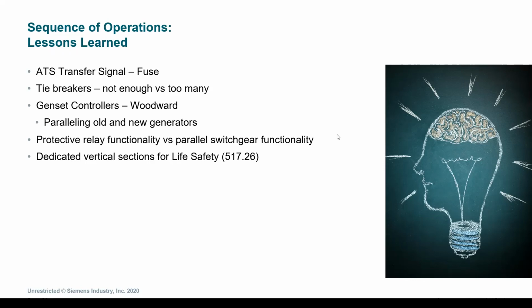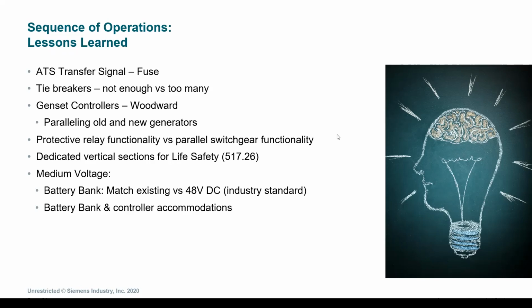Next, it's worth mentioning and reinforcing the requirement, obviously, for Article 700.10, but also for the life safety dedicated vertical section, as this has an impact on the configuration and physical dimensions of the equipment. Next, on those medium voltage applications, it's important to consider the battery bank, whether it's matching the existing batteries on the facility or whether it's bringing in a new classification of size of batteries, such as 48 volt DC. The battery bank and battery charger and controller also need physical accommodations and are important to be considered as part of the early design phases.